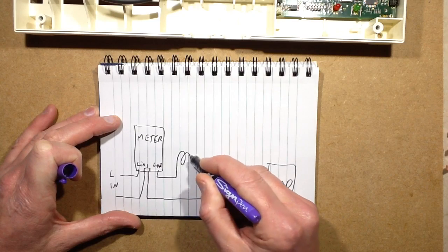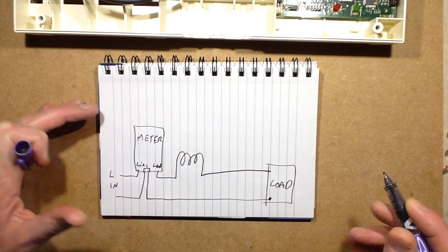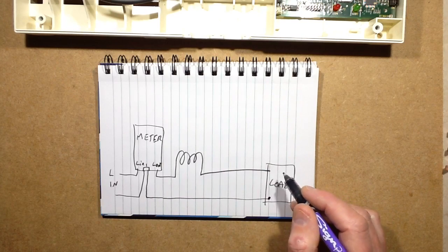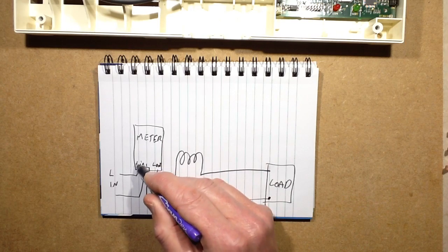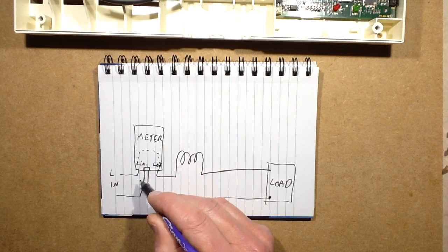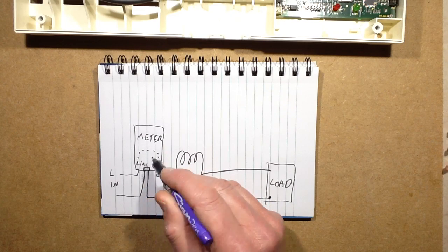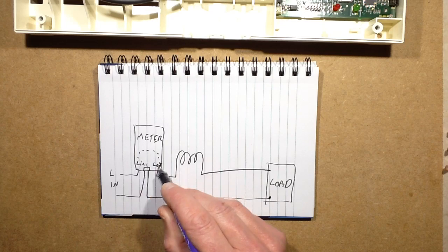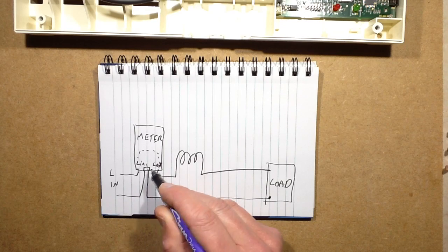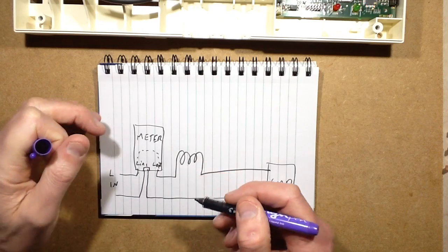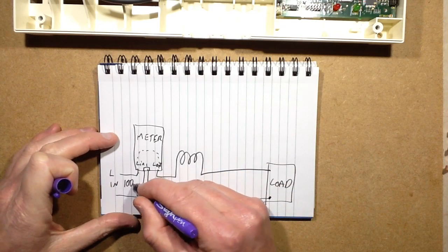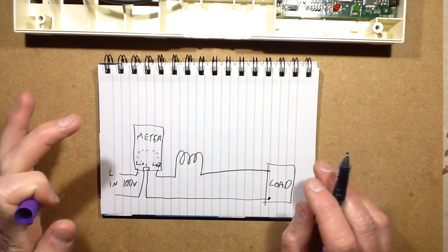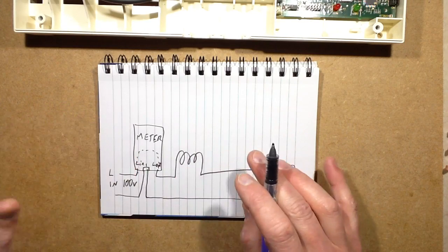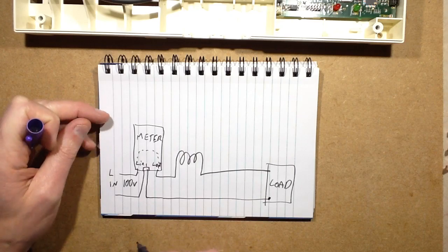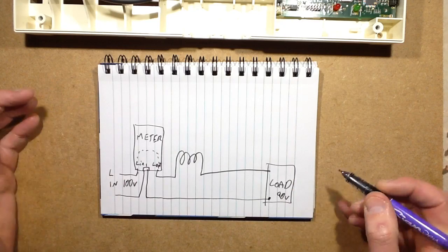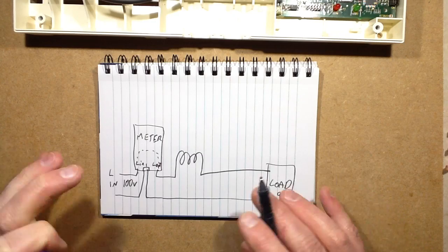And then we've got this buck winding that's in line to the load to drop the voltage. Now the meter measures the amount of current going between live and neutral, and it measures the voltage from live to neutral. So let's go by a standardised voltage of say 100 volts, which is nonsensical. I don't know if there's a country in the world that has a 100 volt supply, but based on the previous sketch, I'll say this is the 100 volt supply, and here's the load operated at 90 volts. Now, if this is an electronic load like a washing machine, there are a couple of things.